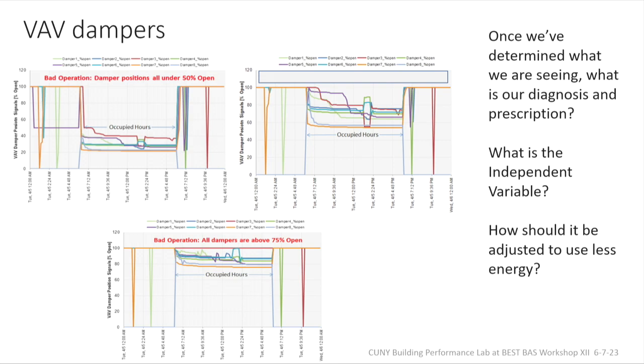By that I mean that all of the zones are not getting satisfied very well. They may be getting, you know, you can see that if we assume this is in cooling mode, the rooms are all in the 80s. So the rooms are starved, the dampers are way open. We don't have enough static pressure in the system.